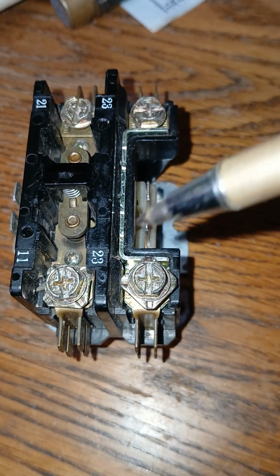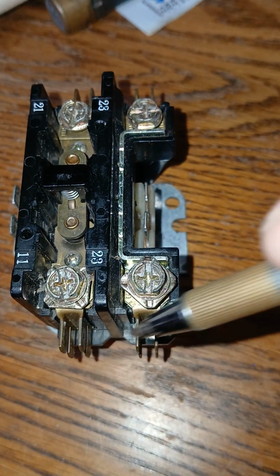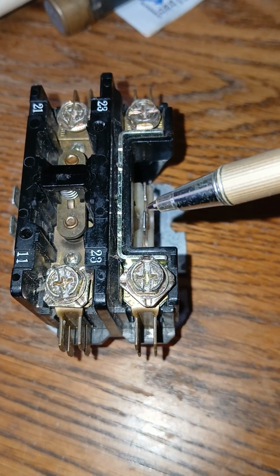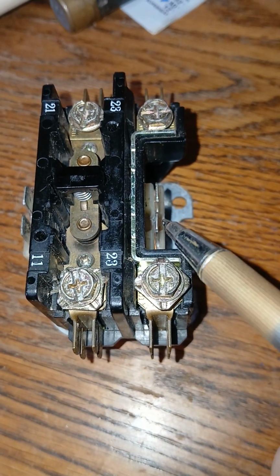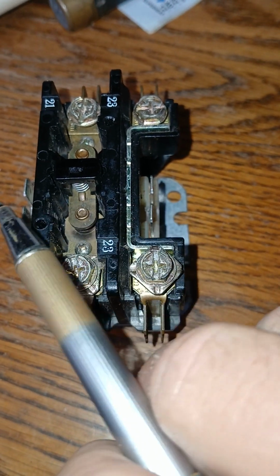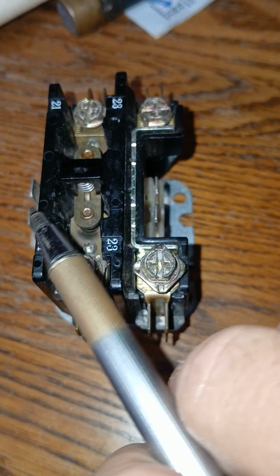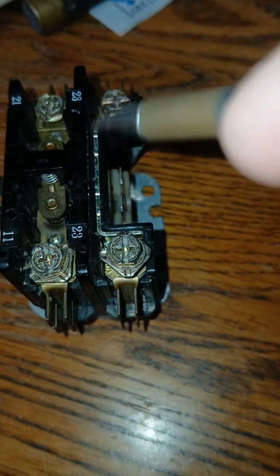Think of this as high voltage, and then these little plug-ins here. Now you have the places where your spade connectors go here, and on top on both of these too. But generally speaking, your low voltage would be on each side. And generally speaking, this would be like a yellow wire or a red wire, and this may be a blue wire, your common wire to return. The red or the yellow would be your hot wire energizing. The blue would be your return for your 24 volt, and then if it's straight up and down, we'll just say going north, this would be your high voltage.